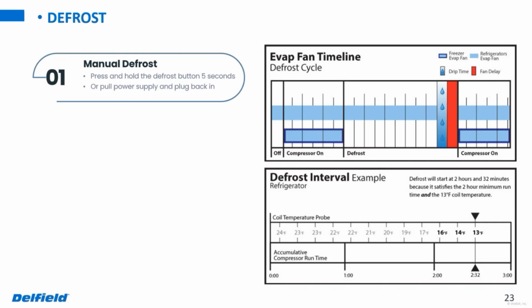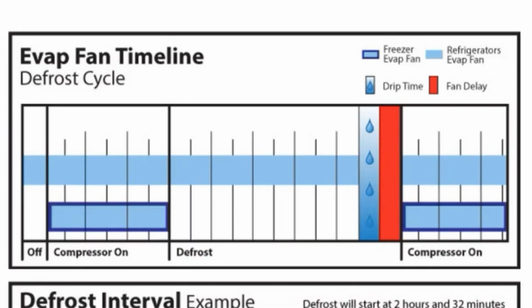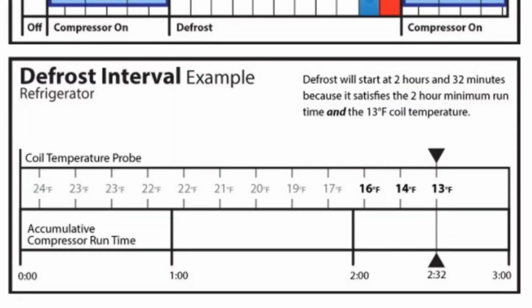The illustrations on the right-hand side show the evaporator, the operation of those. The big thing being with the freezer, during defrost, the fan is off. During a normal off cycle, the fan's going to be off on that as well. The coolers, at least the newer style ones, the fans are going to be running all the time on those. The illustration on the bottom shows nicely how that defrost works. We're using a cooler as an example. So you notice on the bottom here, we got our compressor runtime.